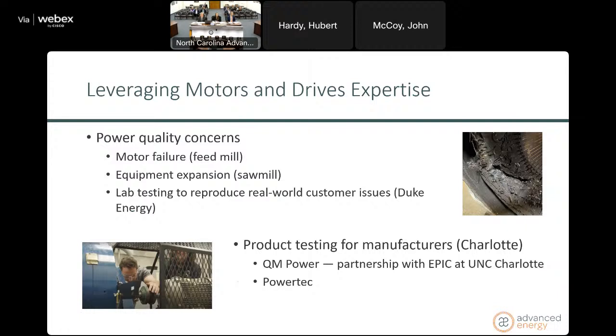After looking at the metering data, we found that the motor failures were not caused by incoming power from the utility. We went through a few different recommendations, but to mention a couple, we gave them solutions to adjust their motor starting practices, their motor type specifications, and their motor storage practices.